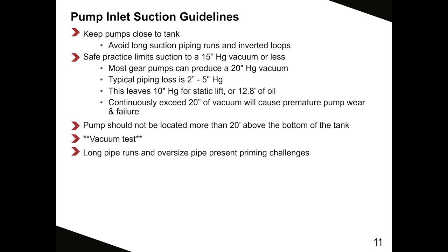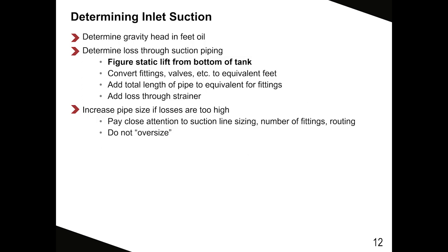Quality positive displacement pumps will create 20 inches of vacuum. We like to design systems with a pump vacuum of less than 15 inches of mercury. As a rule of thumb, pumps will work for buried tanks with a max lift of 20 feet from the tank bottom to the pump inlet. Although code calls for a pressure test on the piping, we also recommend a vacuum test on the suction side of the piping.